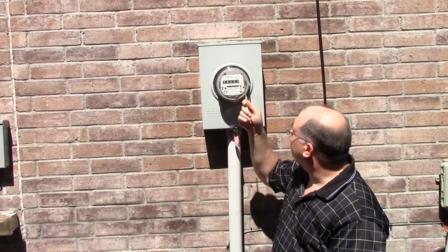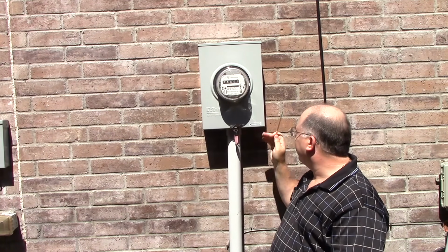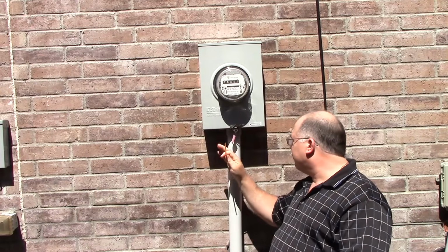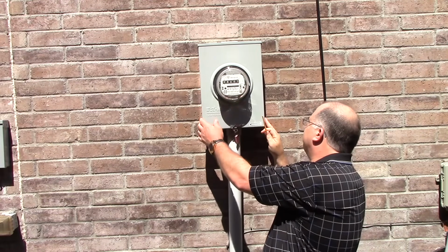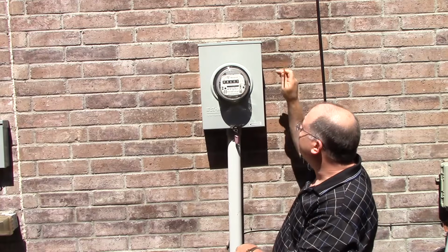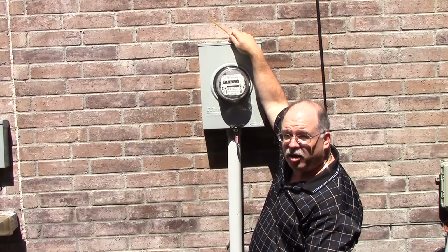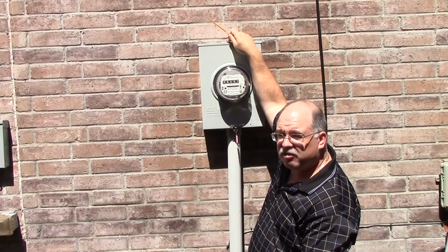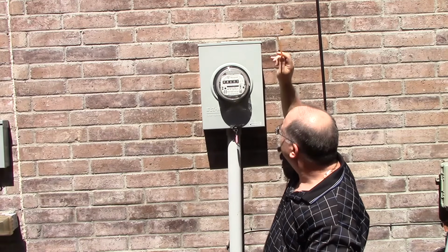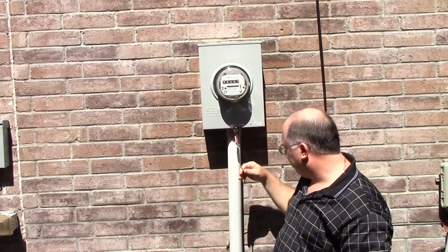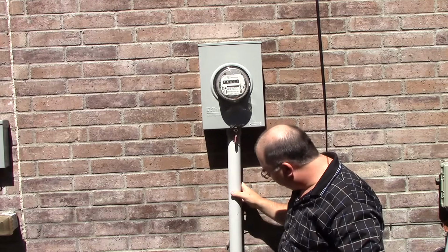So in this case, I know that it's rectangular. I'm looking at all the knockouts. They all are intact. There's no damage. There's no rusting. This is actually tight. It's actually sealed around it. Up on the top, it has a hub cover. The hub is on there. I can actually feel the gasket. Everything looks good here. The meter tab's in place. The raceway here is not damaged.